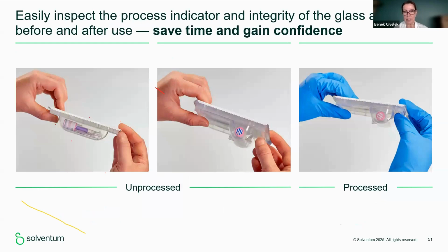Transparency will allow the user to inspect the biological indicator and chemical indicator before and after the process. You can also control the chemical indicator, this is a type 1 process indicator, at the top of the biological indicator, and be sure that it's not exposed first, and then you put it into the sterilizer, and after the process, you see that it has changed, which means that it has been exposed. But then you have to take this BI out, put it in the autoreader, and also inspect the type 4 indicator.